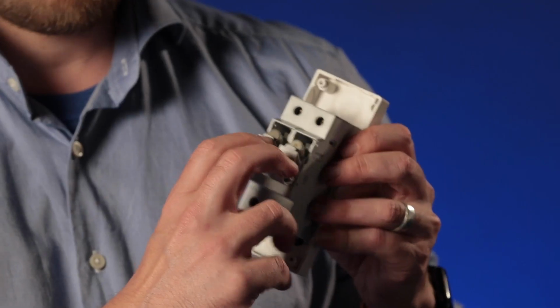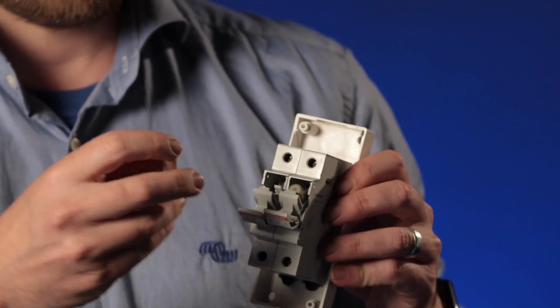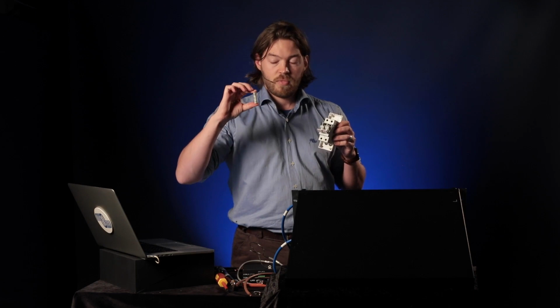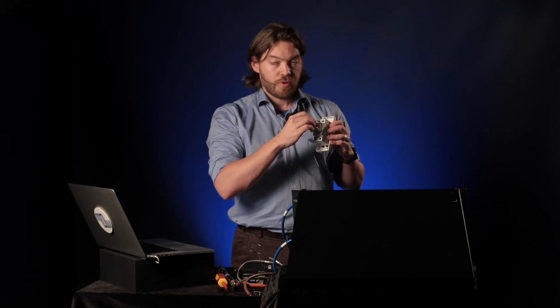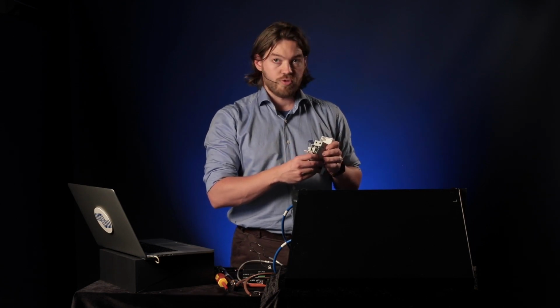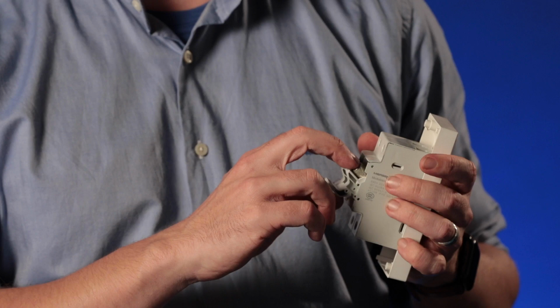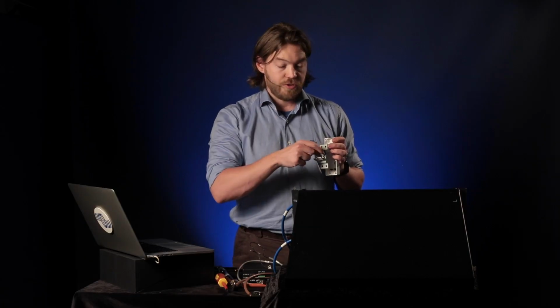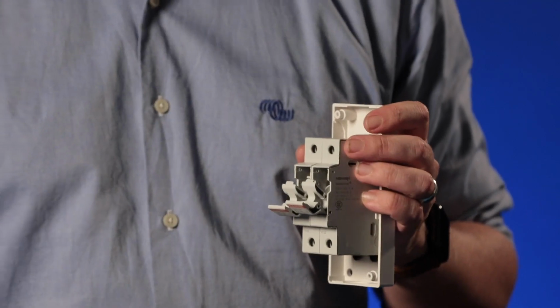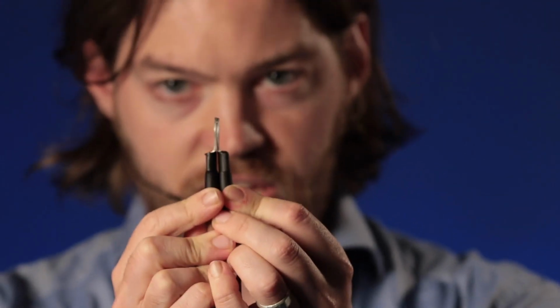Here I've got a ceramic HRC, that's high rupture current ceramic fuse. These are important because of the high inrush currents and general high loads that a MultiPlus will draw. So it's important to use a high quality fuse. To begin with, while I'm getting this all set up, I'm actually going to remove the fuse from the holder just so we don't get any accidental connections. I'm going to go back to back with my connections.